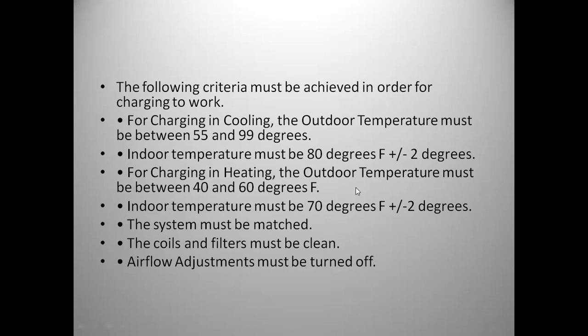For heating, if you're charging in heating, the outdoor temperature must be between 40 and 60 degrees Fahrenheit. Indoor temperature must be 70 degrees plus or minus 2 degrees. A big one is the system must be matched. We ran into this not too long ago.